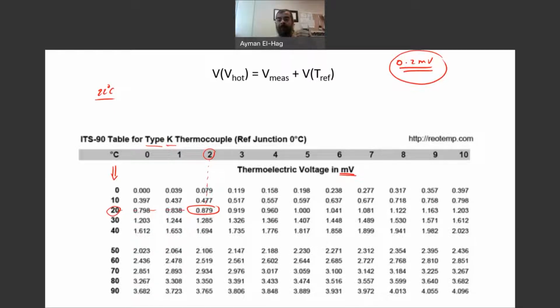Now, we were at room temperature, around 22 to 23 degrees — let's say 23 degrees centigrade. At 23 degrees, the corresponding voltage is 0.919 millivolt. We call this the voltage at T reference, equal to 0.919 millivolt — this is the voltage due to the reference point, which is the other end of the probe.